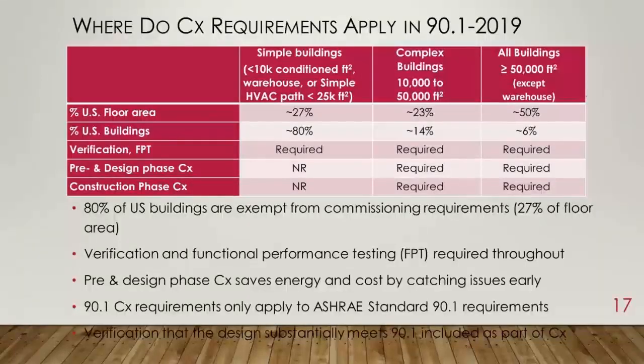So where is that layer of commissioning required? Basically, we started off with 10,000 square feet. That matches up with what 189.1 had adopted. And we did exempt warehouses, and we did say that simple buildings that had simple HVAC control systems under 25,000 square feet would not require that additional commissioning layer. They just had to do the verification performance testing. And that represents about 27% of the floor area, but 80% of the buildings. So 80% of the buildings, these smaller buildings, we get a lot of those, would not have a commissioning requirement.